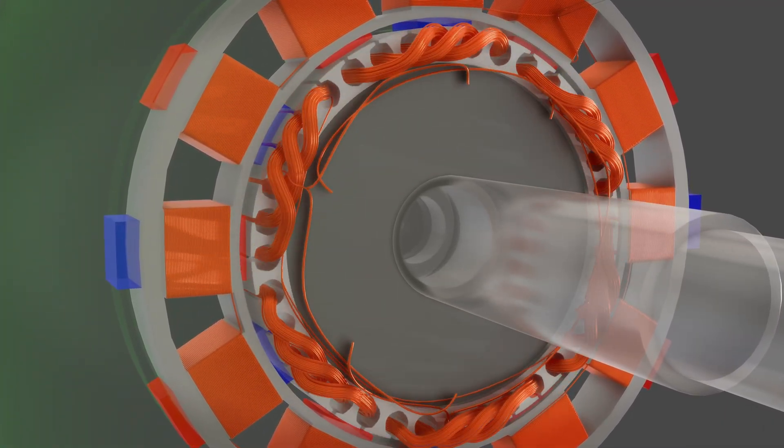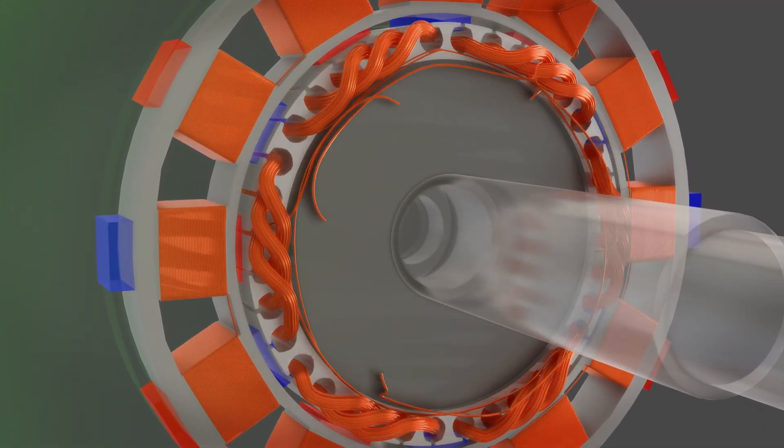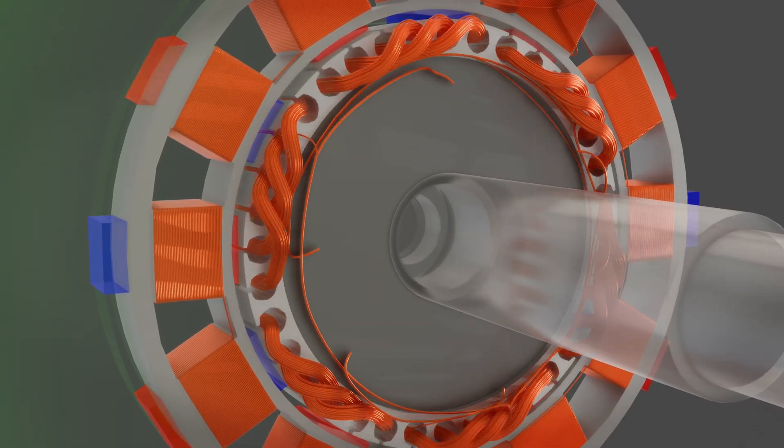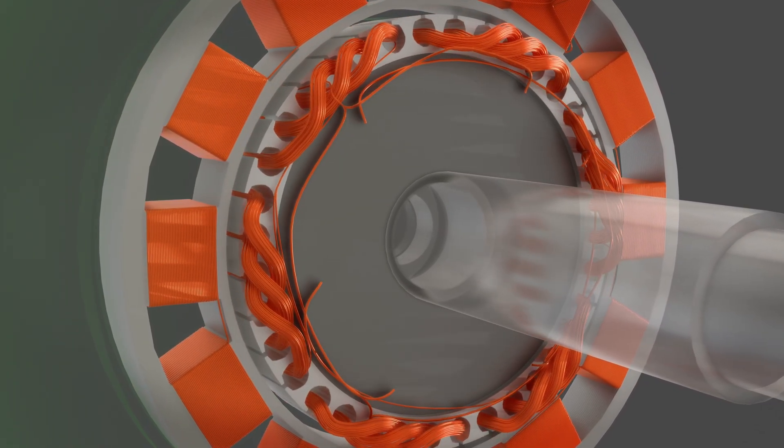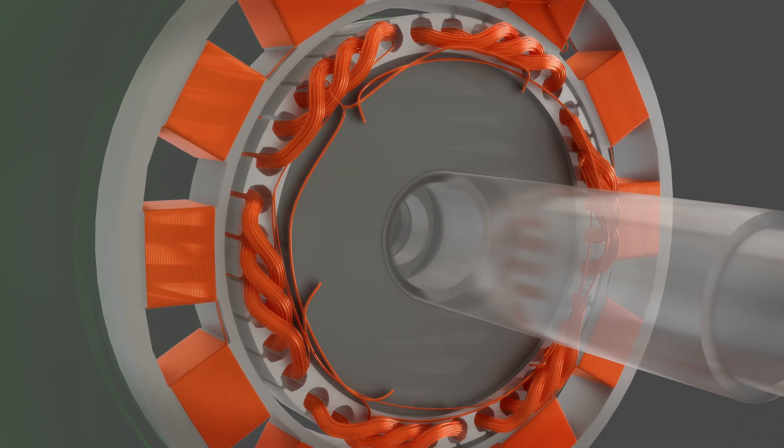When the rotor rotates, it cuts the alternating magnetic fields produced by the exciter stator. The exciter rotor coils generate three-phase AC current, but the main alternator field requires DC current.